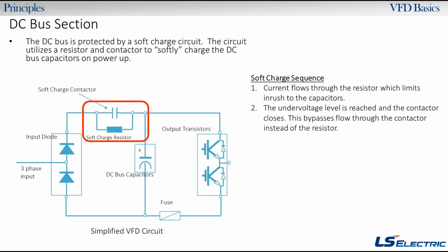So this all happens within a second or less. If you have ever turned on a VFD or turned off a VFD and you hear a loud click, depending on the size of the drive, a big drive is going to have a big click. A small drive, you'll have a tiny click. That's the soft charge contactor turning on and then turning off. Turning on when the VFD goes on, then turning off when it goes back off. Most of these drives are going to have a soft charge circuit in there, and that's just to protect the DC bus capacitors.